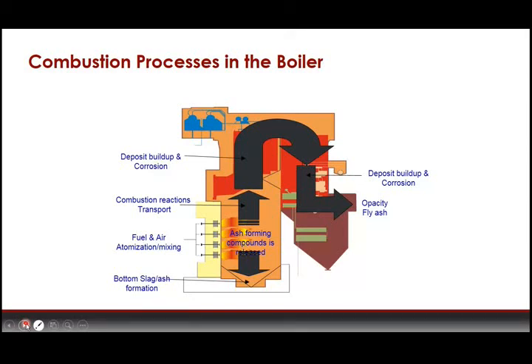Most of our focus is going to be on the boiler — the primary unit that converts the heating value of heavy fuel oil into usable power through the production of steam. In this schematic, we see a cutaway of a boiler furnace. Heavy fuel oil is injected by the oil gun, burns inside, and the superheated air converts water circulating in the heat transfer tubes into steam. That steam drives a turbine to produce electrical power. Spent exhaust gas exits the furnace and travels through emission scrubbing equipment and eventually out the stack.